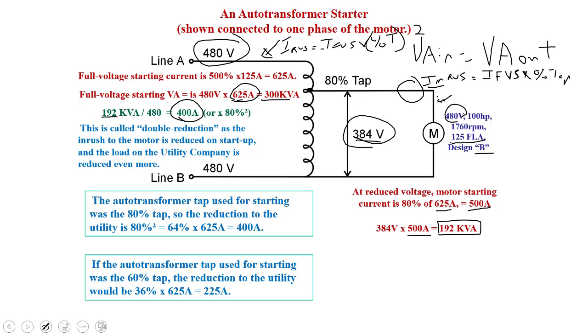The auto transformer, so we can use this for quick calculations. If we set this auto transformer down to the 60% tap on it, we could just go 60% squared times our I full voltage start. We could get our starting current down to 225 amps. Huge reduction from the normal across the line inrush of 625 amps.